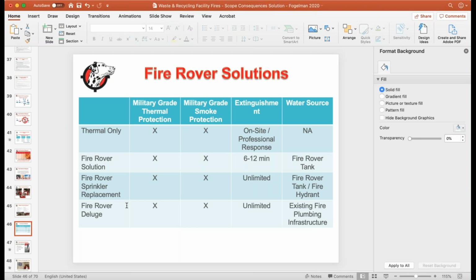The other thing we're doing now is the fire rover deluge system. If you look at waste to energy facilities, it doesn't make sense to have a fire rover tank. What you're trying to do is really deluge the system, because you might have trash that's 20 to 70 feet high. These places fill with smoke relatively quickly, so you need a deluge system that's targeted. We tie into the existing plumbing infrastructure, and we have our monitors and detection and all the different pieces that allow us to safely go after and deluge that system. The minute it turns on, it will go until we have it completely soaked.